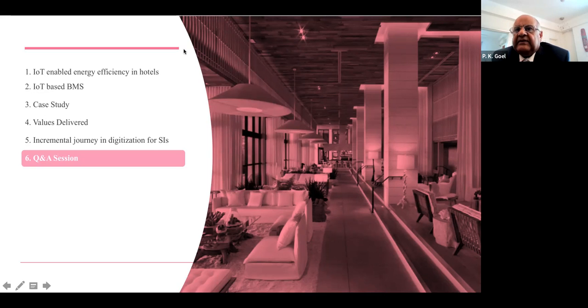And that in turn creates what we call the delta T problem, because with too much flow rate, you get much lesser delta T. So the system doesn't really get commissioned as it was envisaged by the designer.